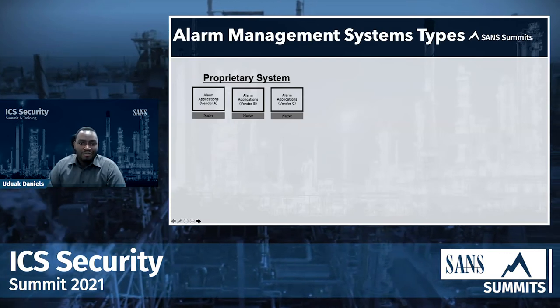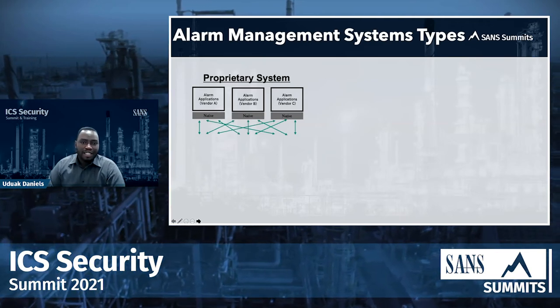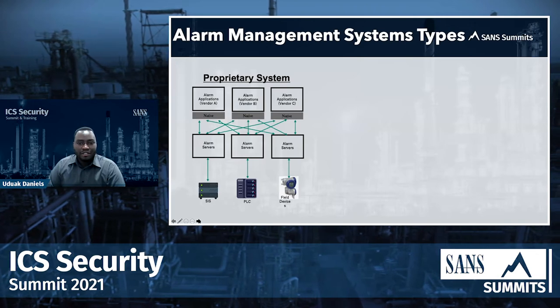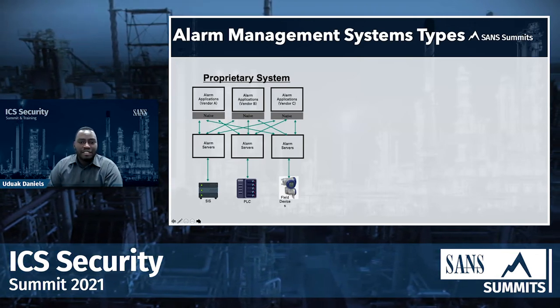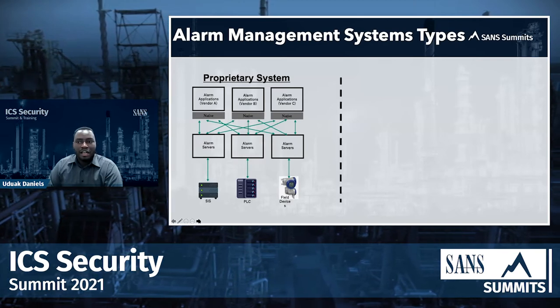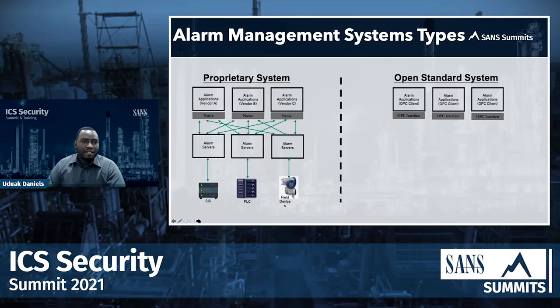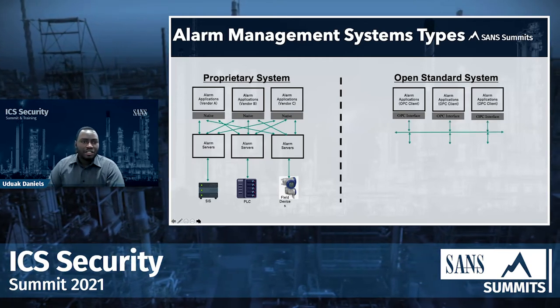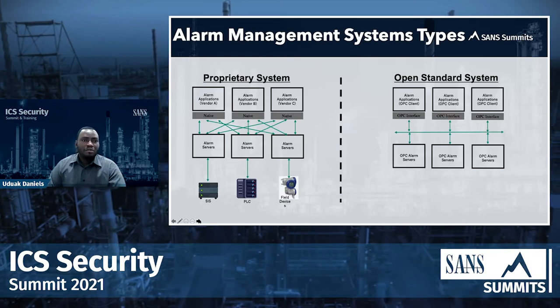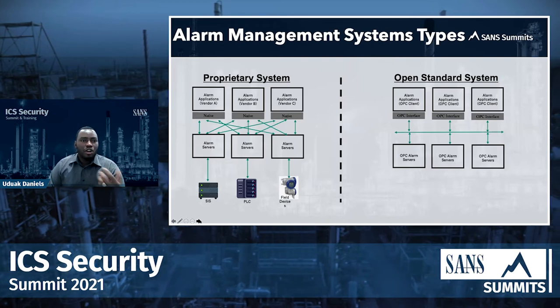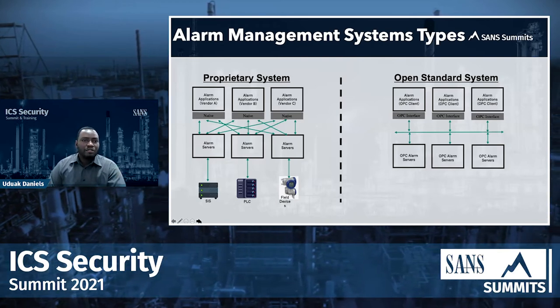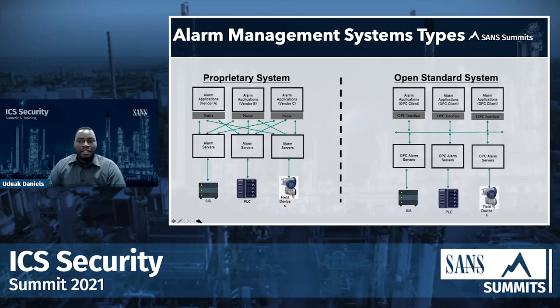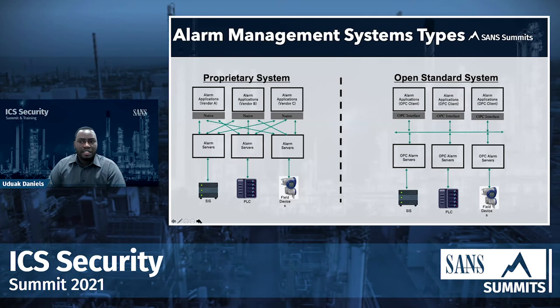In the past, proprietary systems had alarms and applications with native connections — a real hodgepodge of connectivity from alarm servers down to PLCs and field devices. Now with open standards like OPC, the advantage is a one-stop shop: an OPC client communicates on an Ethernet network. Most automation vendors already have OPC implementations and reference models designed into their solutions. It's an open standard and all different field devices and PLCs can interconnect with OPC today.